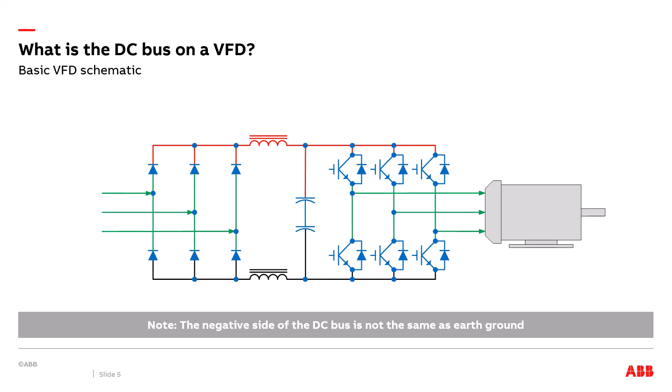Here is a basic variable frequency drive schematic. On the top there in yellow by the red plus sign is considered the positive DC bus. The yellow highlighted line going horizontally on the bottom by the red minus sign is the negative DC bus. It's very important to notice that the negative DC bus is not the same as earth ground. So when we hook up our meter to the drive's DC bus, we just hook up one voltage probe to the positive side and the other voltage probe to the negative side to take the DC bus measurement.